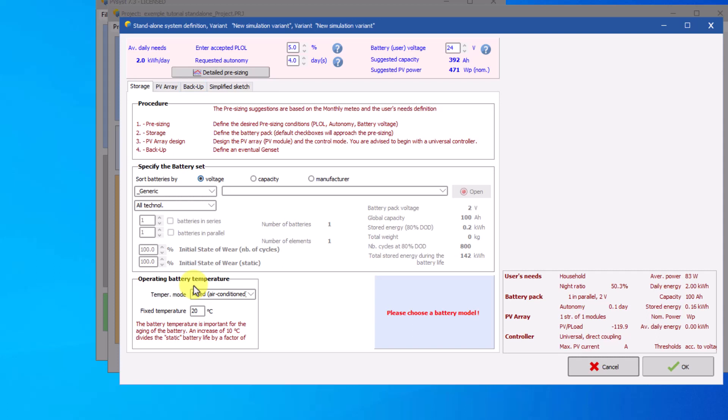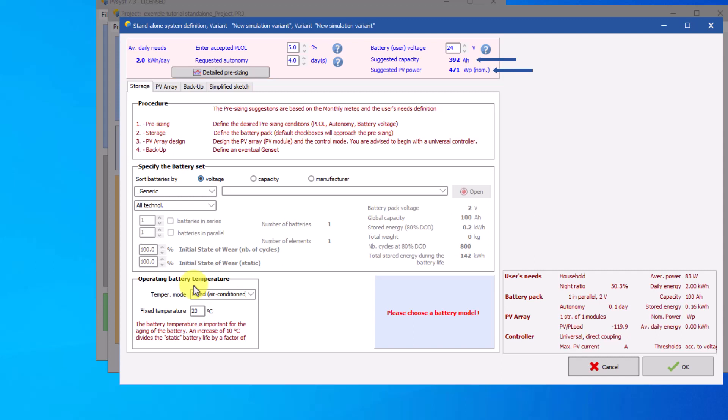Several pieces of advice are important to retain. The pre-sizing tool calculates two pieces of advice. Battery capacity in ampere hours, and PV modules power in watt peak. The PLOL value in percent represents the probability that the user's needs cannot be satisfied.